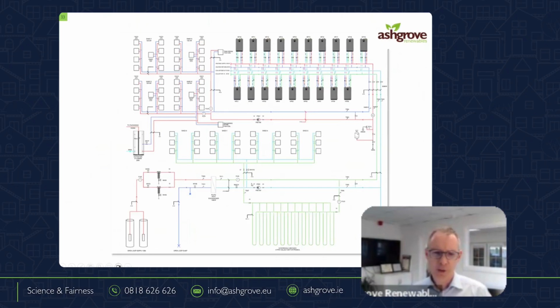And on the cold side, there are three things happening in this case. We have energy recovery from the ventilation. So there's air leaving the building. We'll just say it's at 10 degrees or it might be 25 degrees. If you can imagine the radiator of your car sitting there, air passing over it. If we're refrigerating that as it passes, we take the energy out of it. Now, inevitably, and it's not shown on this one, you have to clean those and it needs to be automatic. Depending on what's passing through, we would sometimes clean it using compressed air. In some cases, you need to use water sprayers onto the heat exchangers. But either way, we'll just say we're taking 200 kilowatts from here.